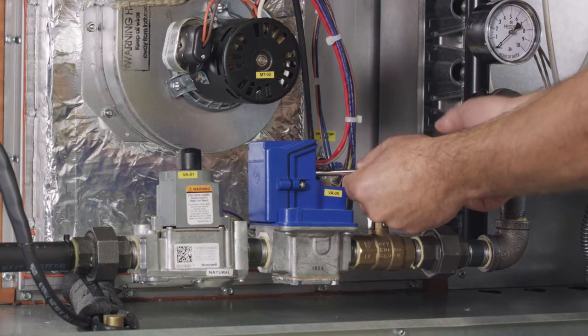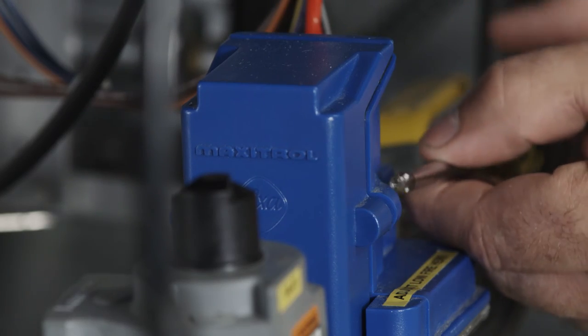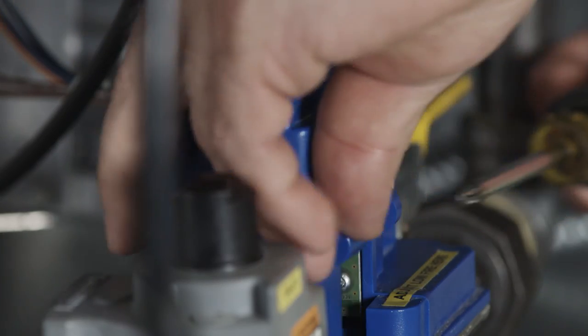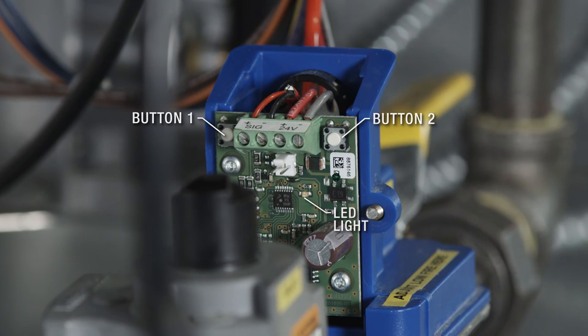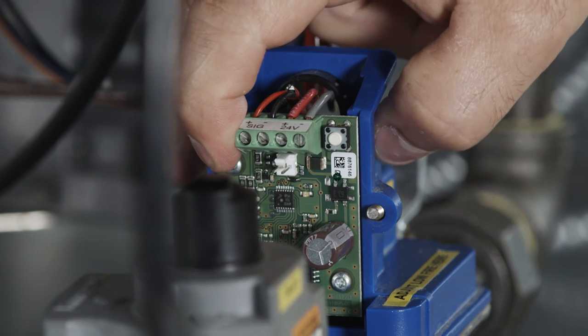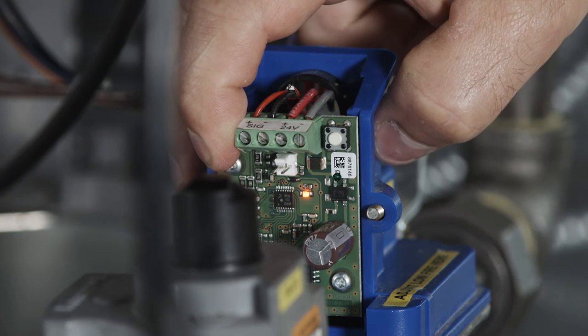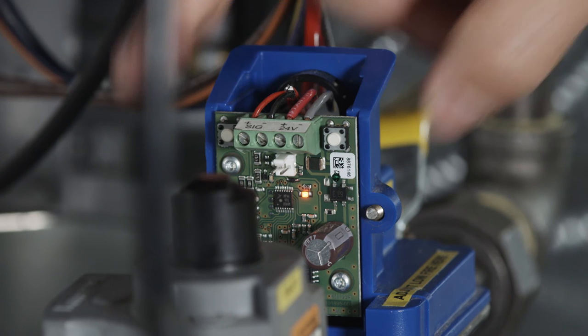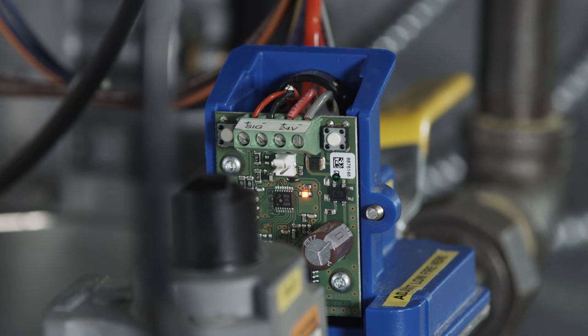Next, remove the cover of the Maxitrol modulating valve. To adjust the high fire pressure, press button number 1 until the LED light is solid red, then release. The valve is now in high fire setting mode.